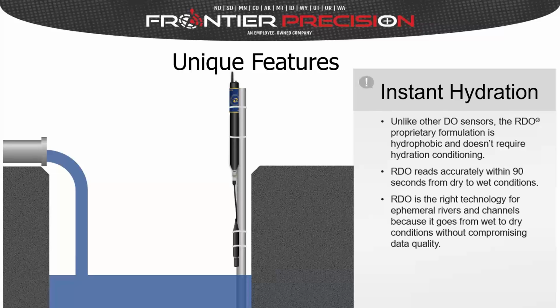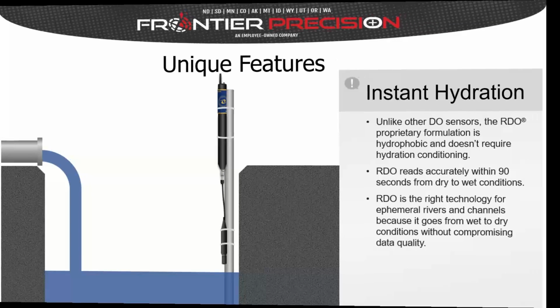So a unique feature of this is because of the formulation of our sensing element, the formulation is hydrophobic, so we don't require hydration and conditioning. And in fact, if that sensor is dry in the field, within 90 seconds, it can go from a dry to wet condition, measuring very accurately. So there might be a lot of applications where you can't control that sensor being hydrated all the time. So this technology that we're using makes that really unique.